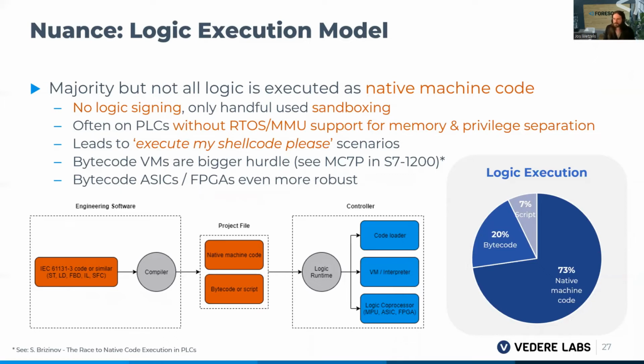In the controllers we looked at, the vast majority execute their logic as native machine code. None of them sign this logic—there may be some authentication on the engineering interface, but no signing on the logic itself—and only a handful apply any sandboxing to this native machine code that gets executed. This is particularly dangerous because most PLCs run without a real-time operating system that has support for memory or privilege segmentation.